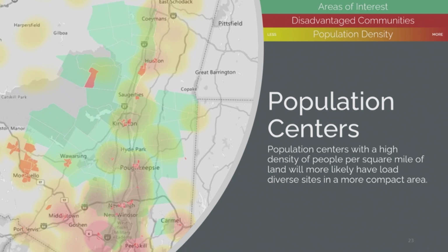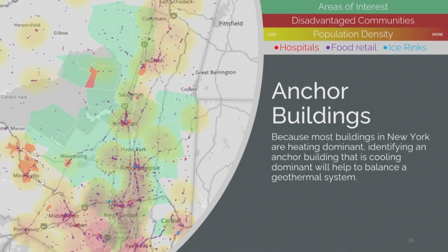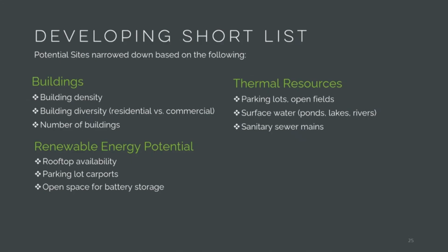And then lastly, we overlaid some anchor buildings. In this climate, we're terming an anchor building as a building with a large cooling load that can help balance out our system, because New York is a heating dominant climate. So taking all that into consideration, we can develop a short list of sites that meet our criteria for load diversity, heating and cooling balance, and also take into consideration whether there's opportunity for other renewable energy like solar PV, and make sure there are adequate thermal resources, whether that's area for vertical bore fields, surface water heat exchangers, sanitary sewer mains, or underground aquifers.